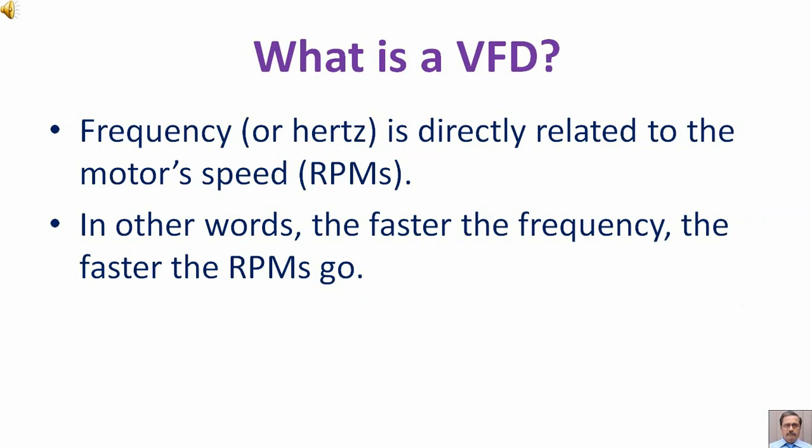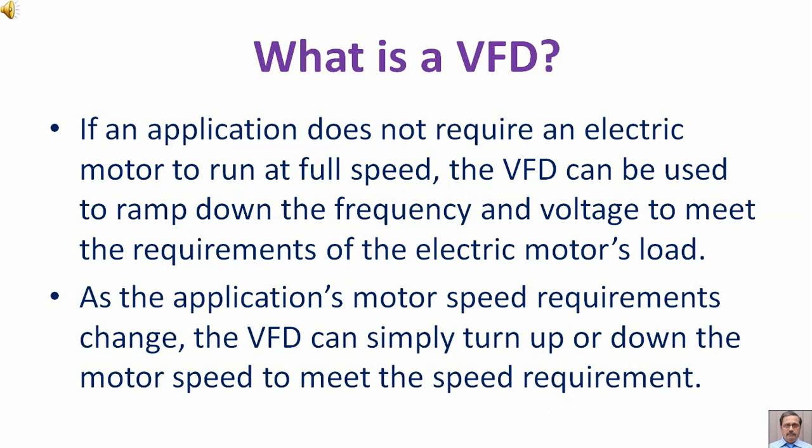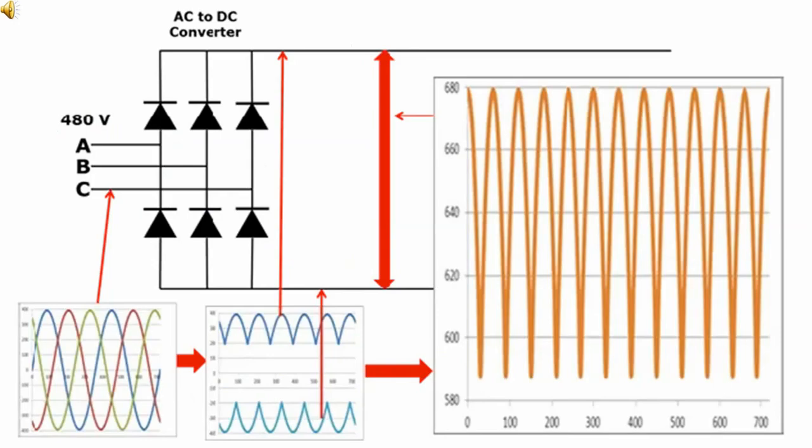Frequency or Hertz is directly related to the motor speed RPM. In other words, the faster the frequency, the faster the RPMs go. If an application does not require an electric motor to run at full speed, the VFD can be used to ramp down the frequency and voltage to meet the requirements of the electric motor's load. As the application's motor speed requirements change, the VFD can simply turn up or down the motor speed to meet the speed requirement.